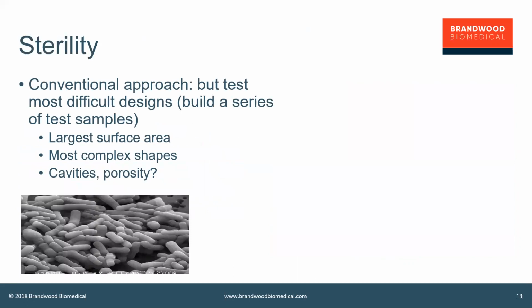Now, actually, whether you've got 3D printed customized devices or mass-produced devices, all the same, you can take the same approach to sterility validation. Sterility validation is usually done by taking worst cases. A good example is making procedure packs, where you might have a number of medical devices within one package, all sealed up within a Tyvek pouch and then sterilized.